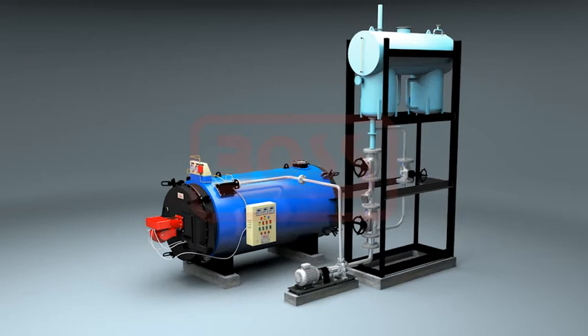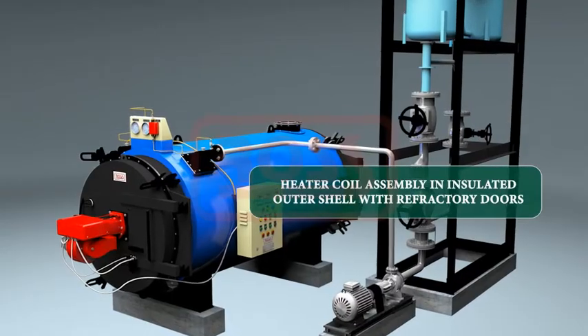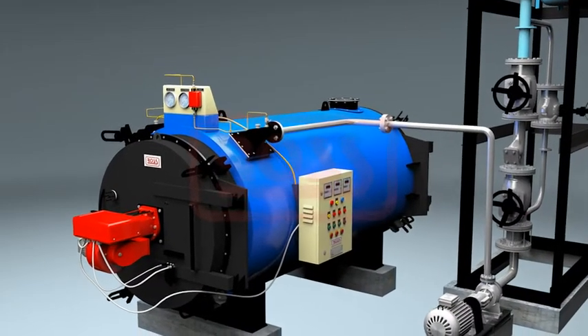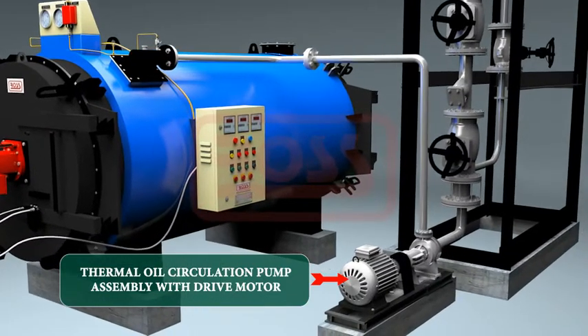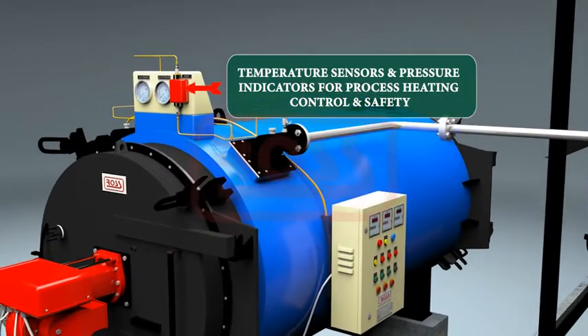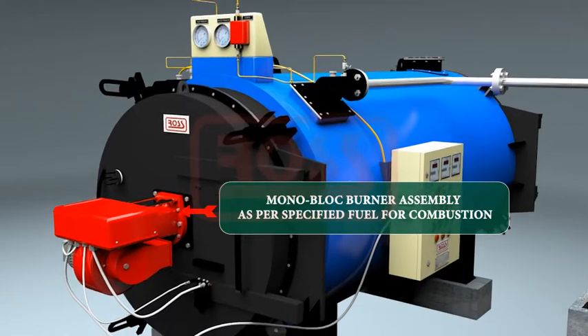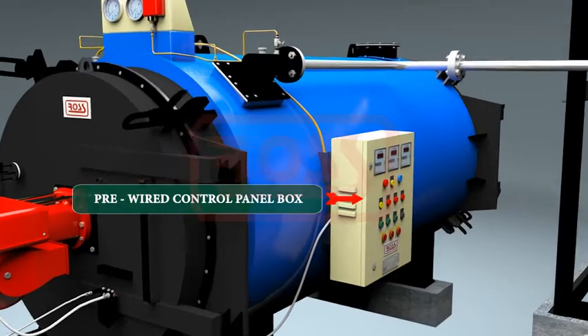These thermal oil heaters are made in conformity with international standards for high temperature control and safety. Each alpha thermal oil heater consists of: heater coil assembly in insulated outer shell with refractory doors, thermal oil circulation pump assembly with drive motor, temperature sensors and pressure indicators for process heating control and safety, monoblock burner assembly as per specified fuel for combustion, and pre-wired control panel box.